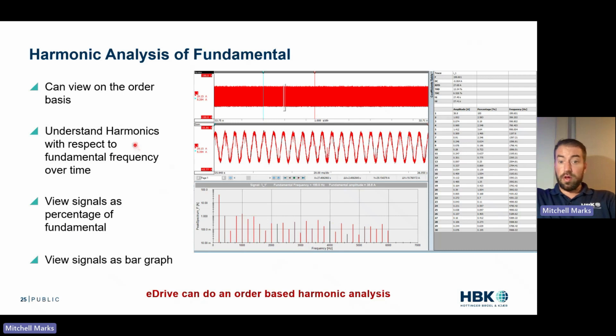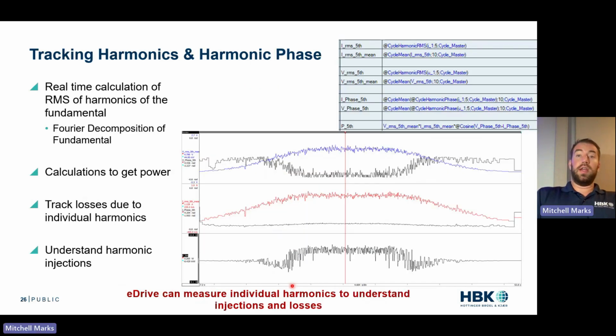You can understand how the harmonics are with respect to the fundamental. You can view the signals as a percentage of the total, and also view the signals as a bar graph. So you can really look visually at two different control strategies and understand what's happening. So this is something that's possible in the eDrive, to do that order-based harmonic analysis. This is really cool. Now, my favorite one is tracking harmonics in harmonic phase.